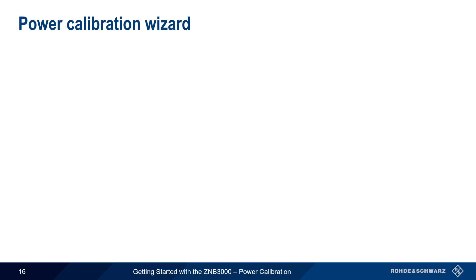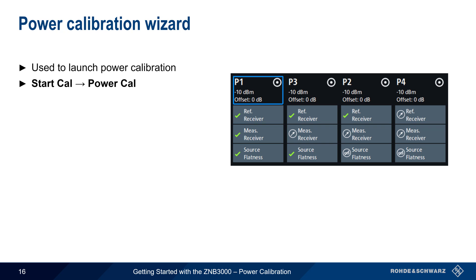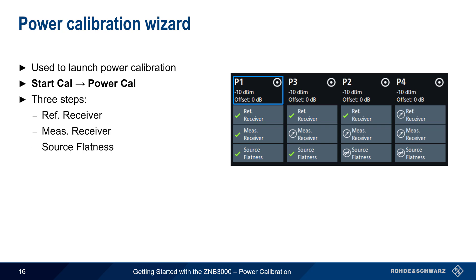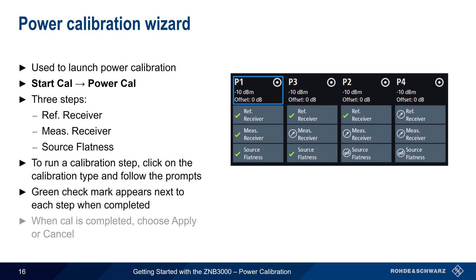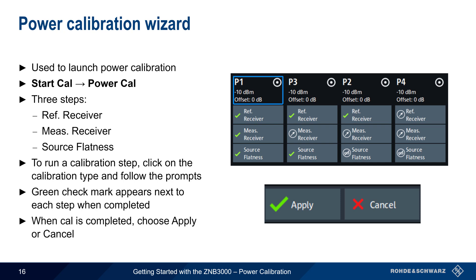Calibration is run and results are observed using the Power Calibration Wizard, launched by going to Start Cal then Power Cal. There are buttons for each of the three steps: Reference Receiver, Measurement Receiver, and Source Flatness. Simply click on the calibration type and follow the prompts. A green check mark will appear next to each step when it's completed, and the Apply button can be used to activate the completed power calibration.